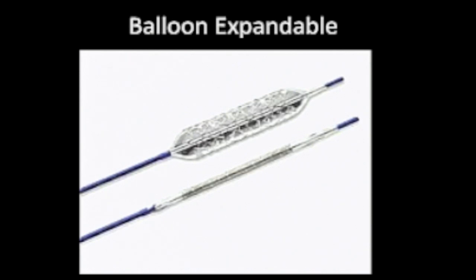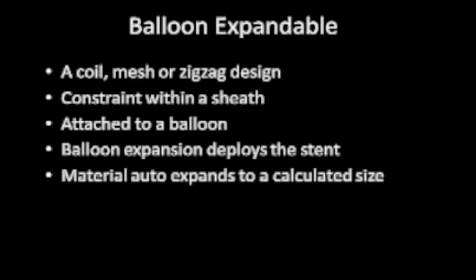A balloon-expandable stent is mounted on the outside of a balloon on a guide wire system. As you pull back the sheath, you inflate a balloon to a certain atmosphere of pressure and it deploys the stent. It's a coiled mesh or zigzag design attached to the balloon, and it expands to a calculated size once you inflate the balloon. These come from the factory with specifications for how much atmosphere is needed to inflate it to a certain diameter.